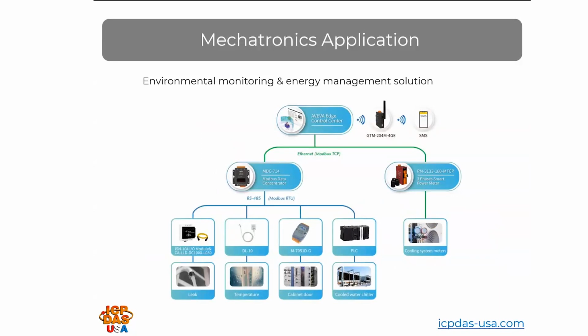Another mechatronics application is environmental monitoring and energy management. I mentioned InduSoft SCADA software. We also have Aveva SCADA software, and that comes with many different kinds of communication drivers. This one's using the Modbus TCP driver, which communicates out to the GTM-204M-4GE over the cellular network, and it allows for the PC to broadcast out SMS messages based on the conditions of the application.